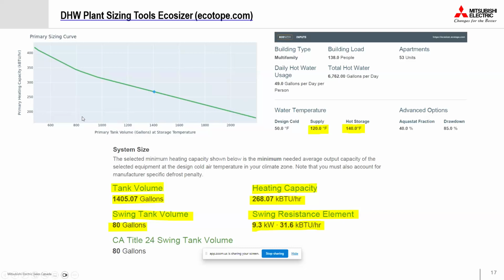But if I don't have the space, then maybe I want to go with less storage capacity, 800 gallons. And in that case, I will end up with like 350,000 BTUs per hour for the equipment sizing. So that's how you can play with that graph and find out the best solution available for your design.